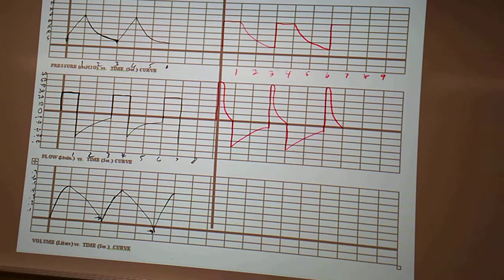So how do you know the flow, even if you're in volume control, if you're using a square? This is fixed. This will never change. You change compliance, you change resistance, this will not change. In a pressure-based breath, the shape of that is going to dramatically change when compliance and resistance change, because the flow and the volume are going to change. Flow and volume are variables in a pressure-controlled breath.